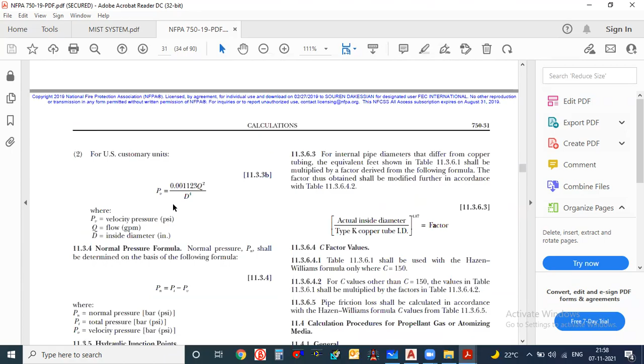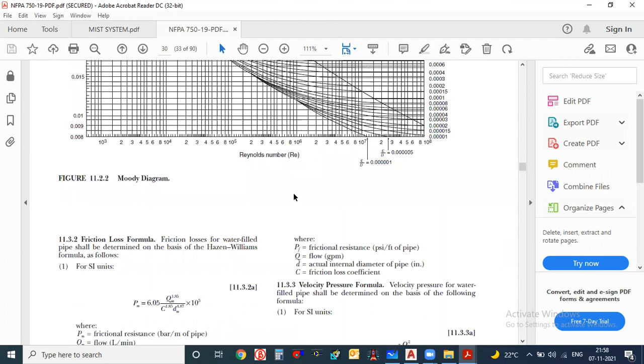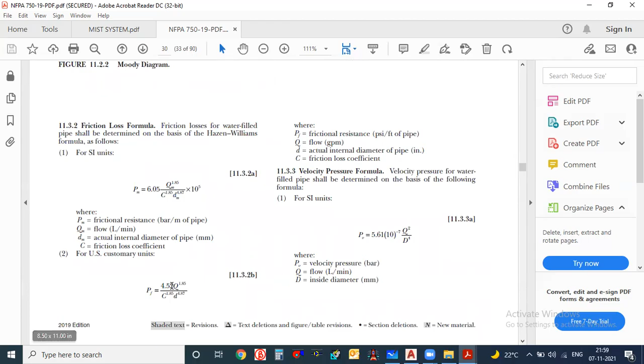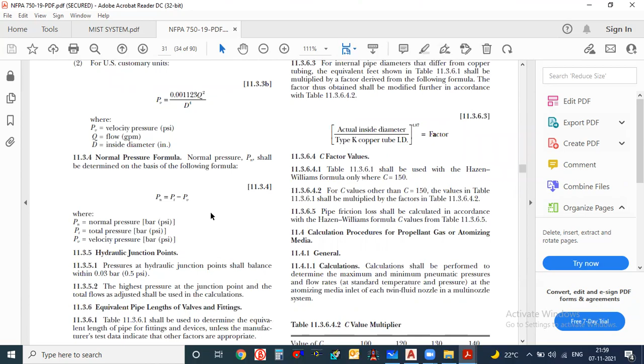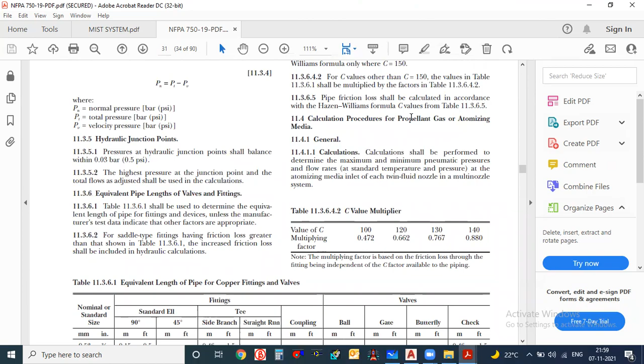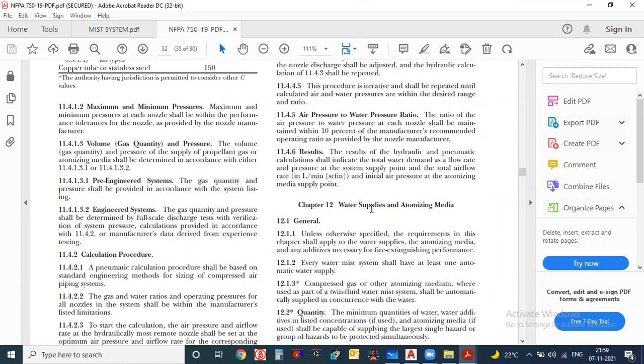Copper pipe here. And there is no K factor given here. We haven't found anything related to the K factor. They have given only the Hazen-Williams formula, the one which we have used. C factor is given, but K factor is not given here. And here they have given some calculation procedures for propellant gas or atomizing media. Different methods are also given here. You can just leave this. Just understand that it is the same procedure we have done in NFPA 13. Water supply and atomizing media.